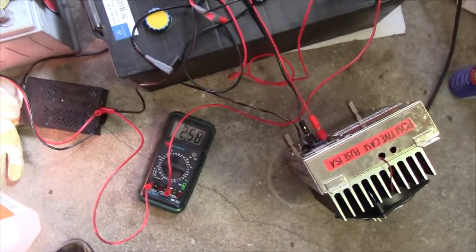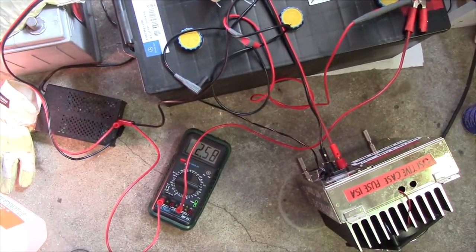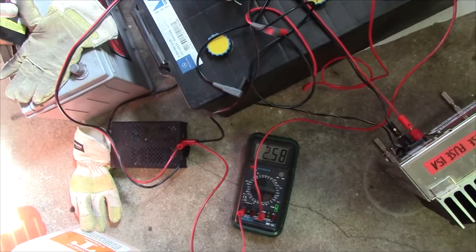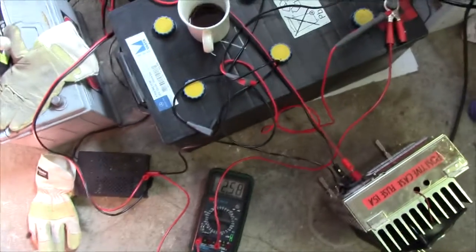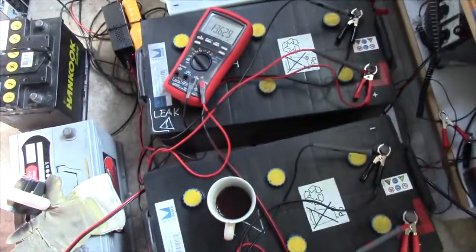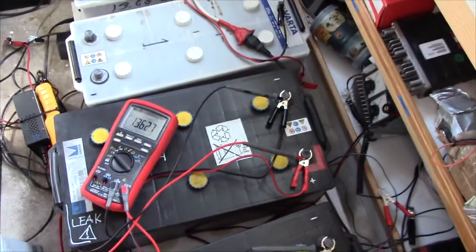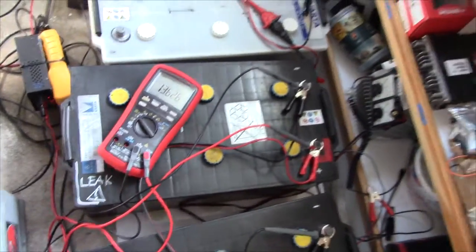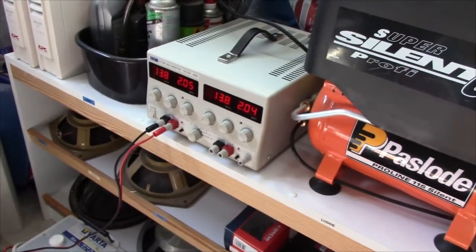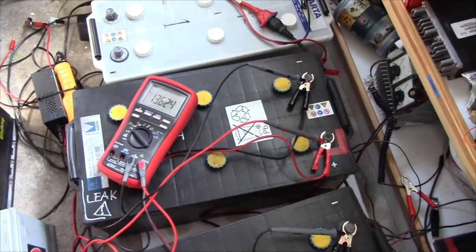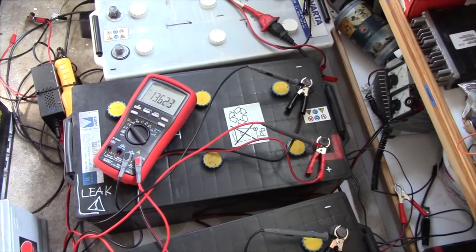It's the next day and this guy has been charging overnight for about 12 hours maybe, with both chargers maxing out at around 15 amps or so. And it's starting to get kind of full. I'm about to head into town on a few errands and I think I'm going to be bold. I just took this one off the float charger, it's been floated at 13.8 volts. I'm just going to turn on a load test and hope that I'm back within the maybe 9 hours it'll take if it's got any kind of similar capacity to this one.